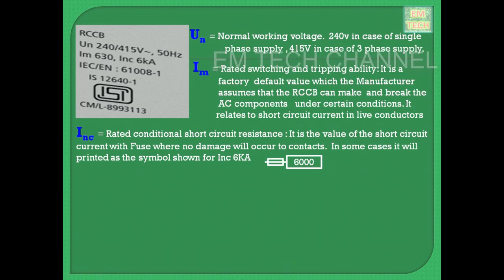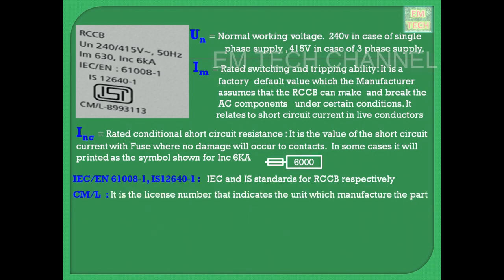Next, there come the IEC and IS standards. IEC means International Electrotechnical Commission, and IS is Indian Standards. The IEC standard is 61008-1, and it speaks about the RCCB, and Indian standard IS 12640-1 also speaks about the RCCBs. So points in both of these standards are taken into account, and these RCCBs were manufactured accordingly. Next, the CM/L. The CM/L is the license number. It will be of 7 digits, and it indicates the unit in which the part has been manufactured.